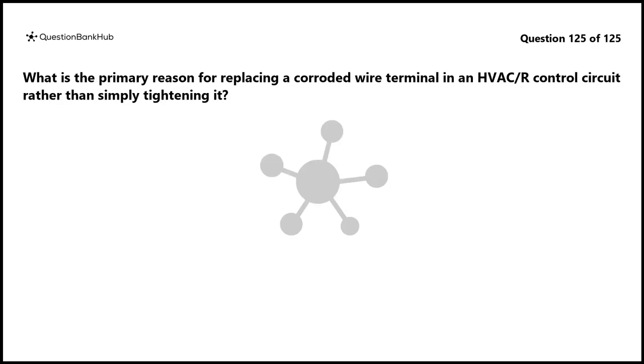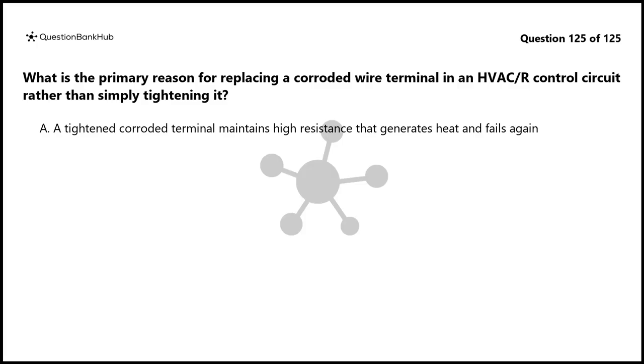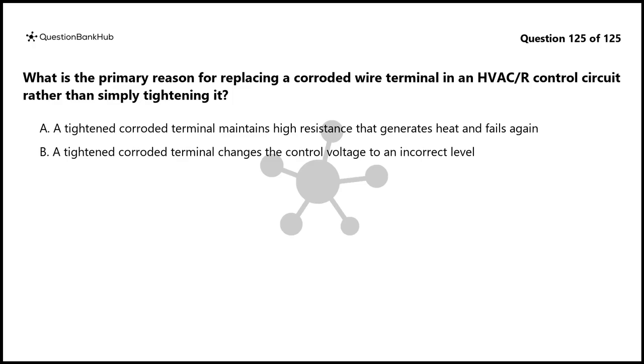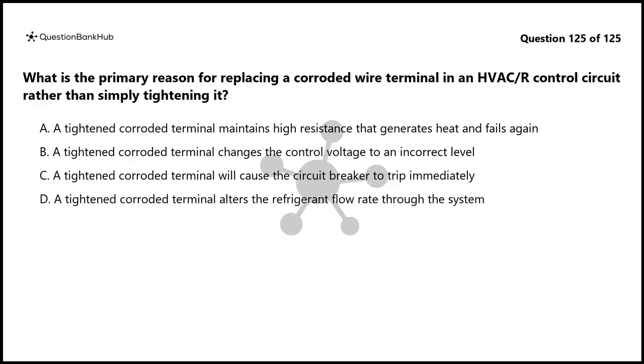Question 125. What is the primary reason for replacing a corroded wire terminal in an HVAC/R control circuit rather than simply tightening it? A. A tightened corroded terminal maintains high resistance that generates heat and fails again. B. A tightened corroded terminal changes the control voltage to an incorrect level. C. A tightened corroded terminal will cause the circuit breaker to trip immediately. D. A tightened corroded terminal alters the refrigerant flow rate through the system.